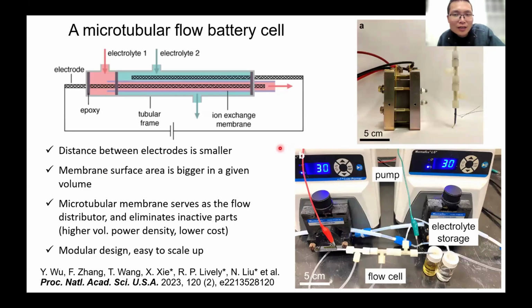What we innovated is making the power module lower cost in the flow battery, since the power module takes up a large fraction of the cost. We reduced the size and cost of this module to make the flow battery system more cost effective, by using a microtubular configuration: the membrane is in a tubular shape, with an electrode inside the membrane and another electrode outside.